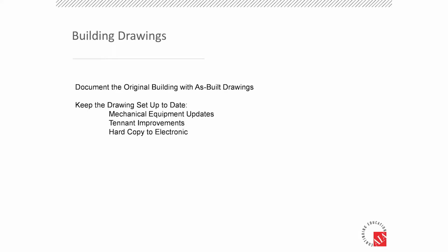Final item is the building drawings. So building drawings, you start with a decent set of as-builts at building occupancy date. Then you try and keep those up to date. If you are getting mechanical equipment updates, if you're replacing cooling towers, pumps, that should be noted in your drawings. If you have tenant improvements, they're going to modify the mechanical systems on the floor. That should be rolled into the set as well. And finally, if you're in an older building and you do have a hard copy, we really want to try and get that electronically, whether it's scanned or you contact those original design firms to get their AutoCAD files over to PDF.